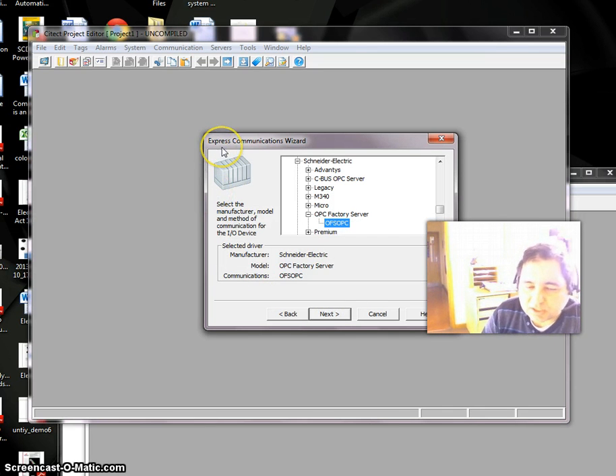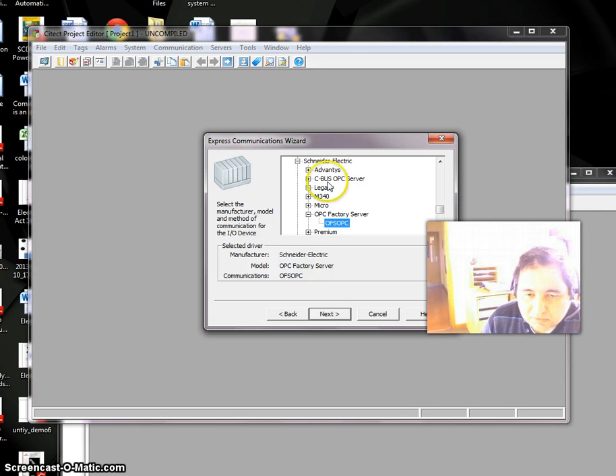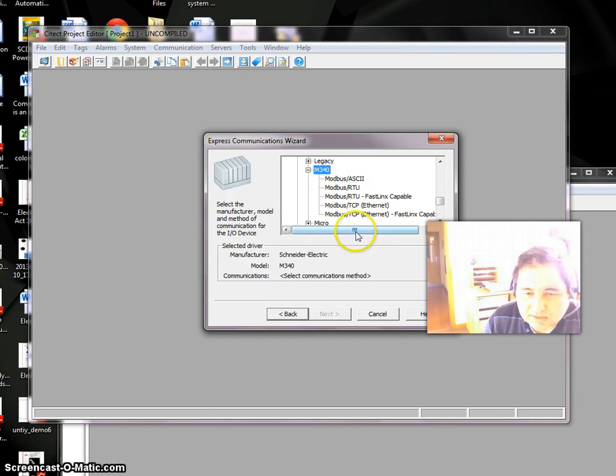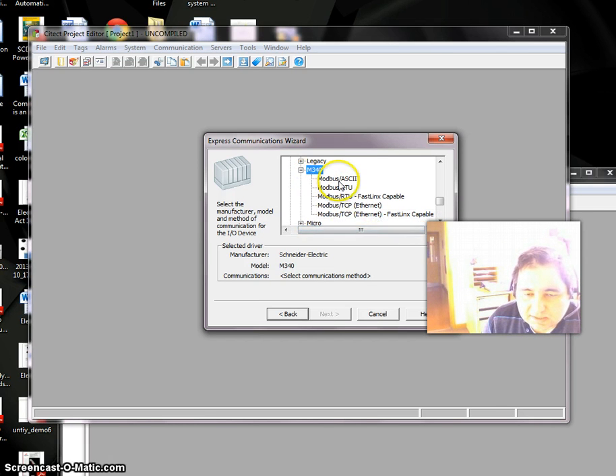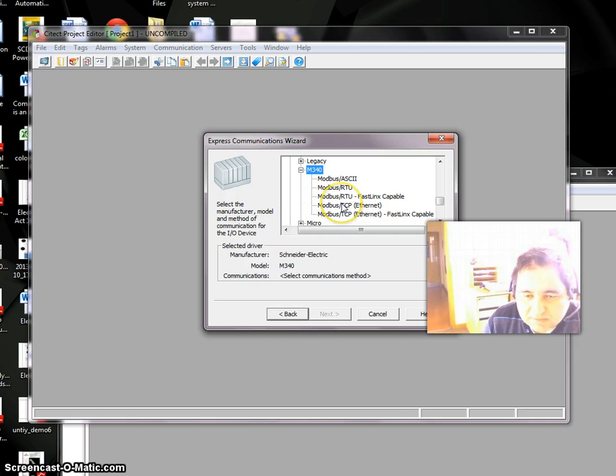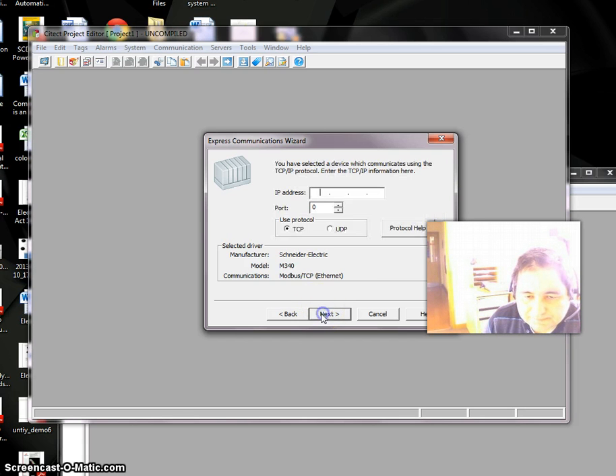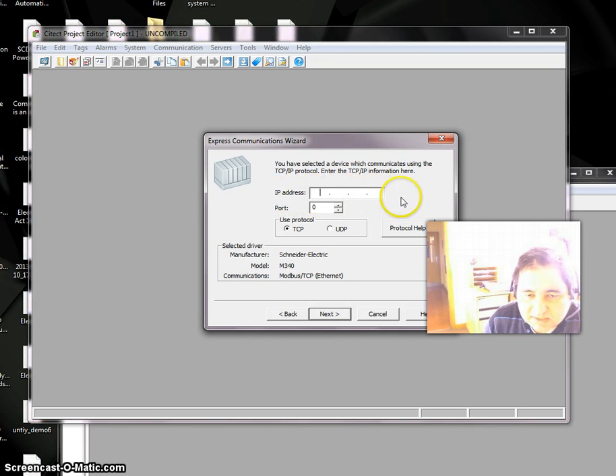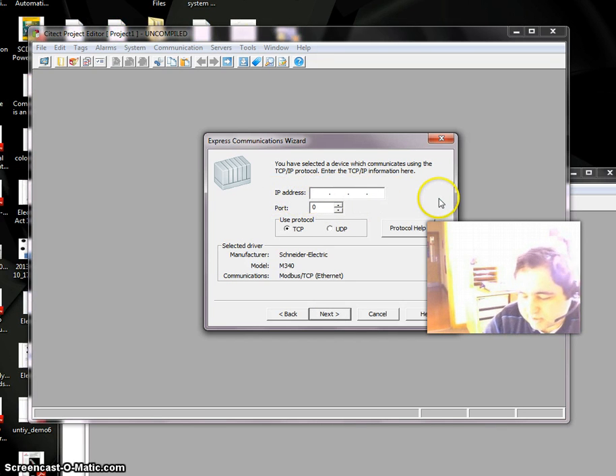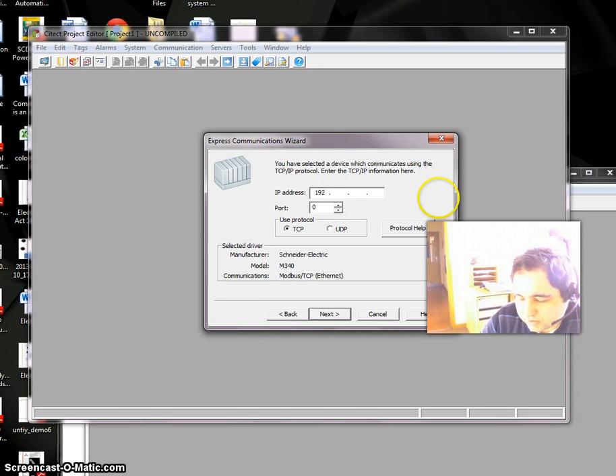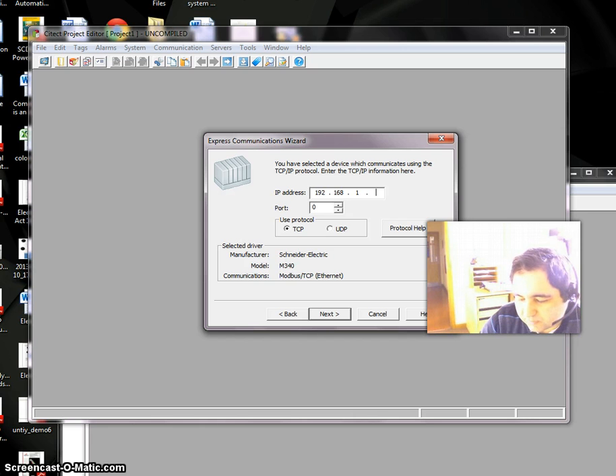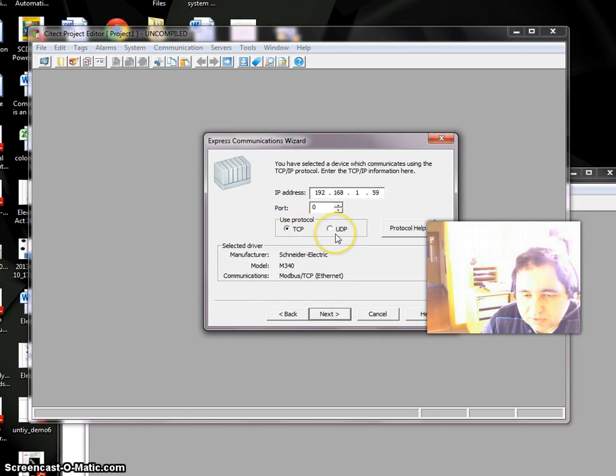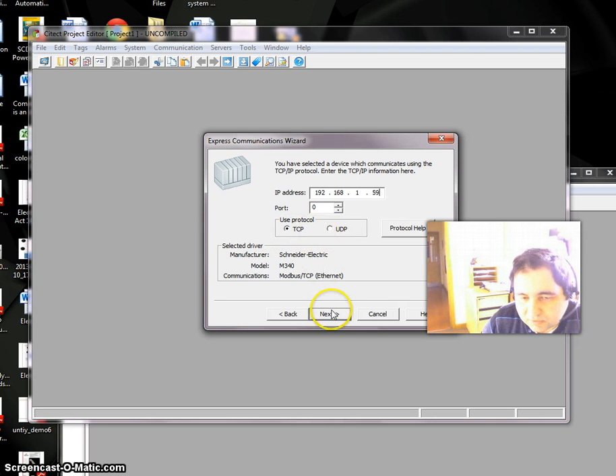We'll go for External IO. The next question is what is your device. If our PLC is M340, click on M340. Then answer the next question: which driver do we use for communication? If you use TCP/IP Ethernet, select that. The next question is the IP address. Let's say it's 192.168.1.59. We can set the port and decide on the protocol—TCP or UDP. UDP is faster than TCP, but TCP is more accurate, so TCP is more useful for automation.